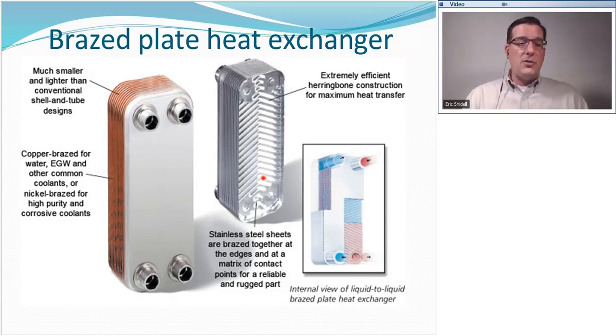It's really great for keeping dissimilar types of water, either different makeup of water or different pressures, separate from one another. For example, boiler water, you don't want to drink it. You don't want it mixing with your domestic water. But if you want to use a boiler to heat your domestic water, a heat exchanger is necessary to keep those two water streams separate. Also, your domestic water is going to be a higher pressure than your boiler water. Lots of reasons why we don't want those two water streams to mix. And in those applications, a heat exchanger is the way to go.